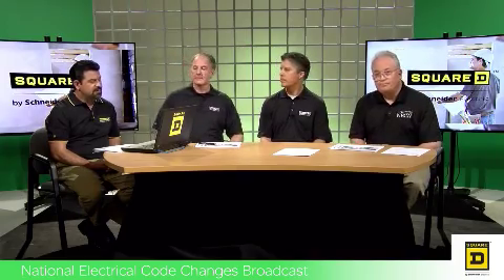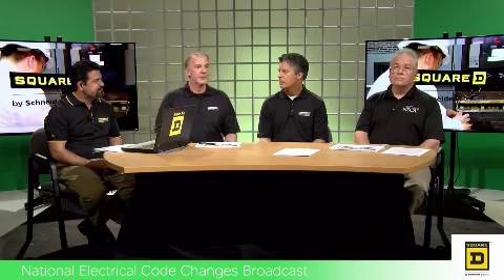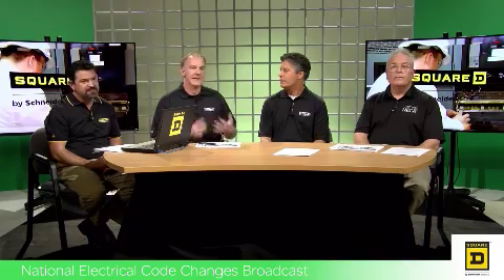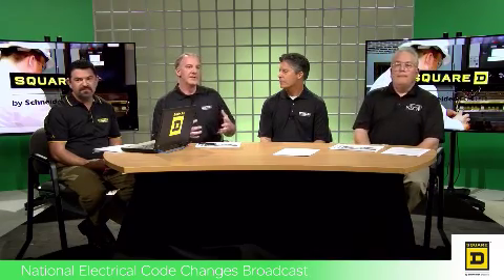Excellent topic, excellent topic. So Alan, we'll move on to the next topic, arc energy reduction in section 240. All right, 240.87. We have a list of items in 240.87 that continues to support safety with the electrical contractor and reducing the arc energy of the system, right? For 1200 amps and above. So I mean, one of the things here is continuing to recognize technology that can do that function, and so we've added a couple of items to the list, and those items are really already built-in functions to the overcurrent device. In most cases, you have an instantaneous setting on the breaker.